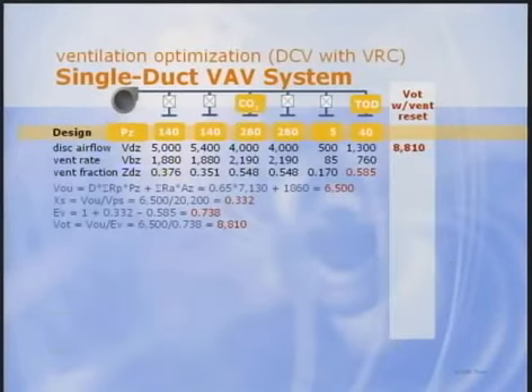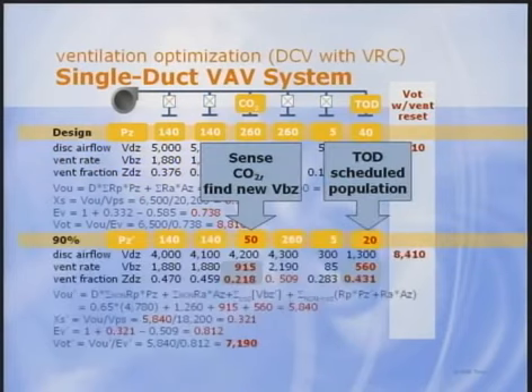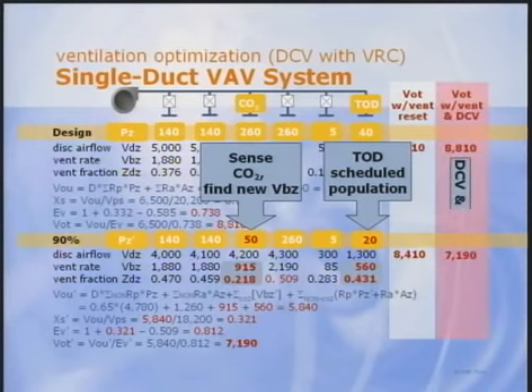Let's look again at our 6-zone system, this time using a CO2 sensor in one zone and a time-of-day schedule in another zone. We see that at design, nothing changes, but at part load, a CO2 controller determines the required outdoor airflow in one zone, and a time clock determines the effective population to find the required outdoor airflow in another zone. Using these lower than design airflows, we use the multiple zone equations and find the current required intake airflow. But after doing the calculations, we find that at this example load condition, the system only needs 7,200 CFM of outdoor air, which is significantly less than the 8,800 CFM needed at design.